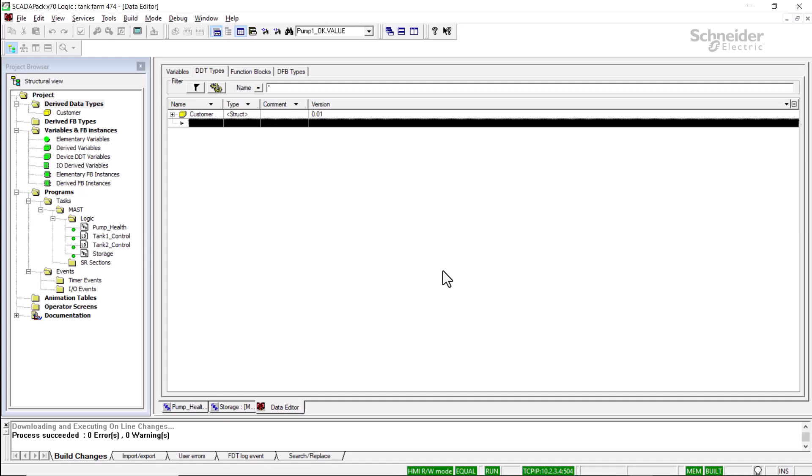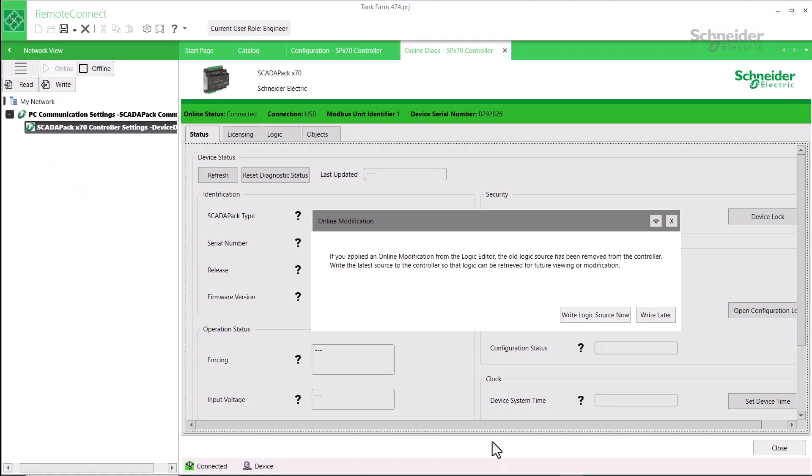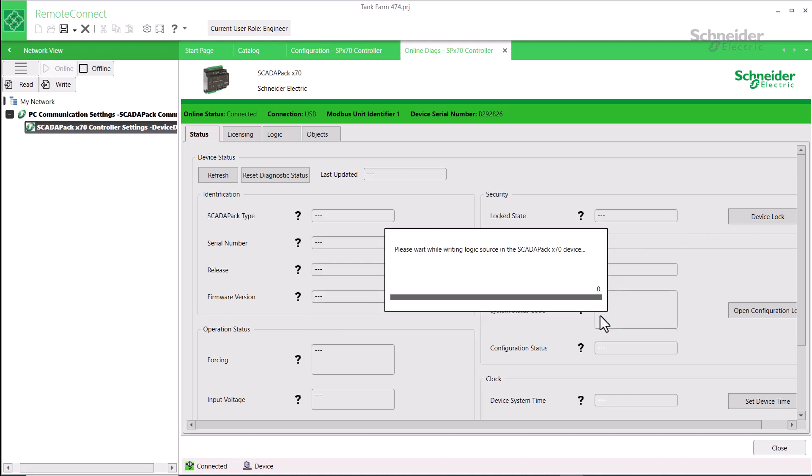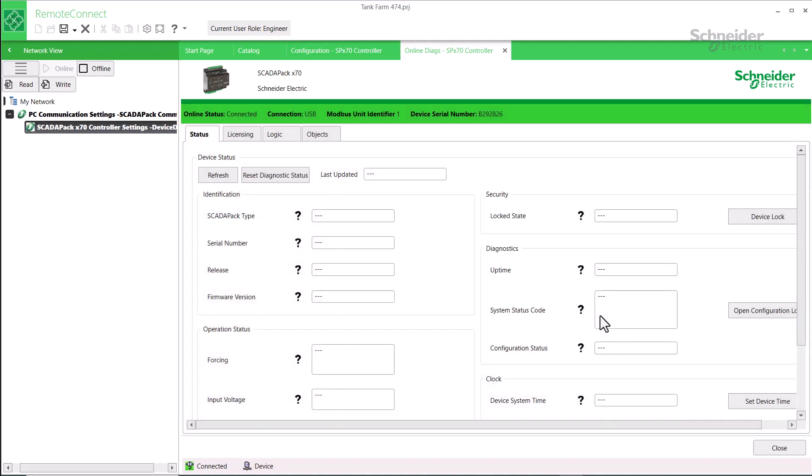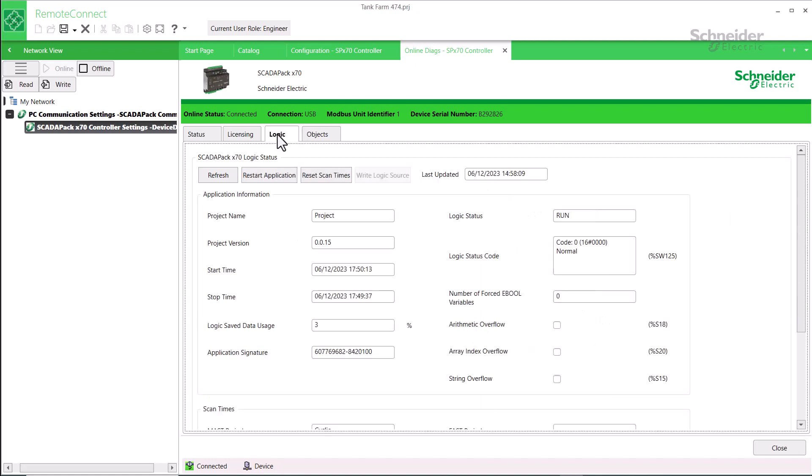Now as I'm done online editing, I'll go back to RemoteConnect. And in RemoteConnect, it's prompting me to write the logic source now. As I'm done with editing, I will write it now. Remember that if for any reason in the past, the logic source file was not written to the SCADAPack, you can go to the logic tab and click the write logic source button. Finally, I'll click the save button to save the updated application to my computer.